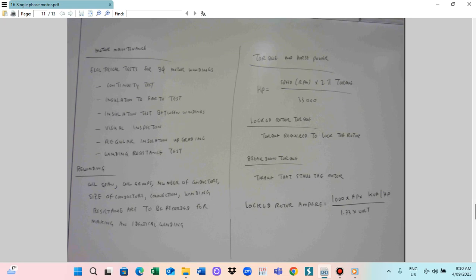Especially, industrial motors very seldom use a single winding. In this case, you use windings in parallel, two or three windings together, to rewind the motor. So this is one thing. Another thing is that we also utilize star-delta connection, which is for the big motor. So all the data needs to be properly taken down, and the insulation class is also important, which you have to take.